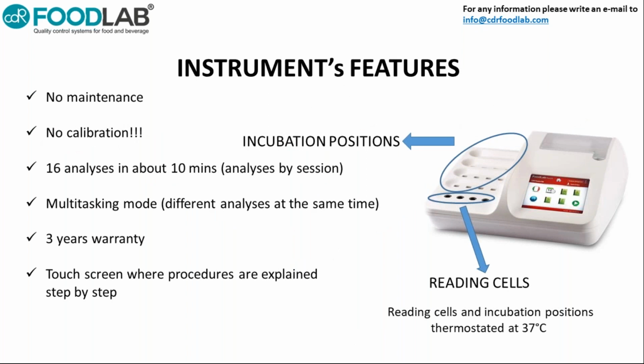Okay, what are the instrument features? As I told you, we don't have any maintenance to do on our analyzers. You don't need calibration. You are able to perform analysis in two ways. Here, as you can see, we have an incubation part, and in the front of the analyzer, you have a reading part with LEDs as wavelength sources. So this means you can perform 16 analyses at the same time in about 10 minutes. So you can carry out the same parameter on different samples, okay?